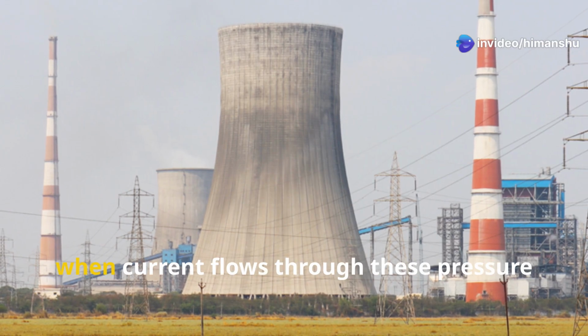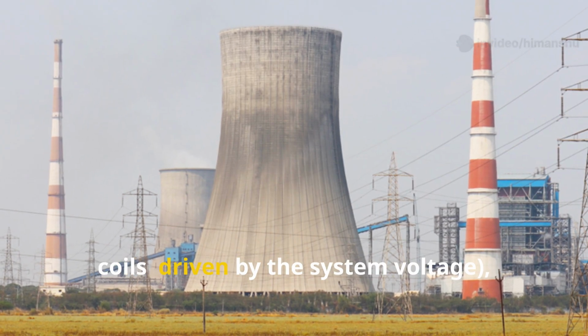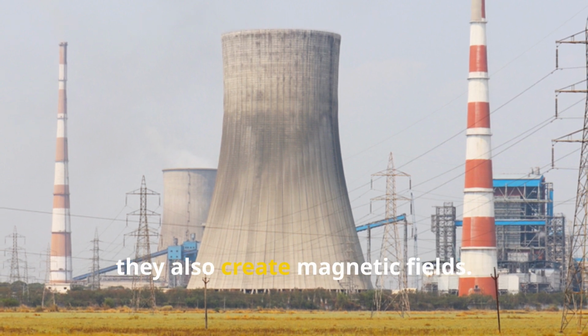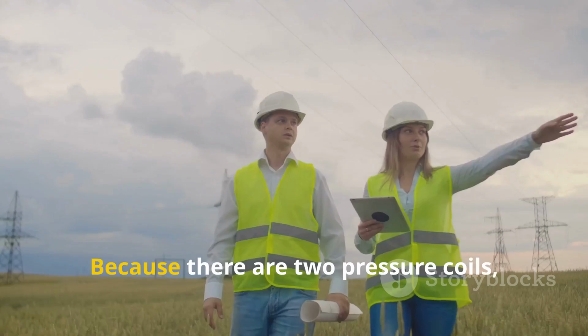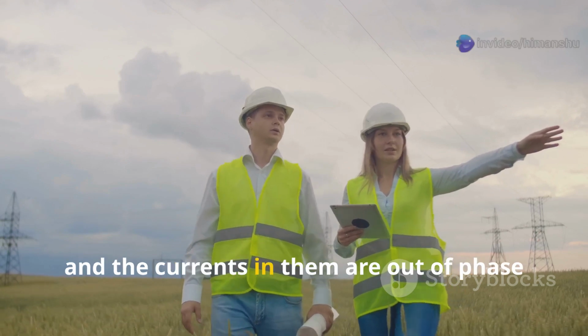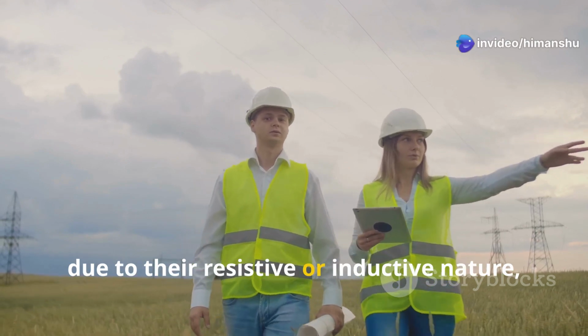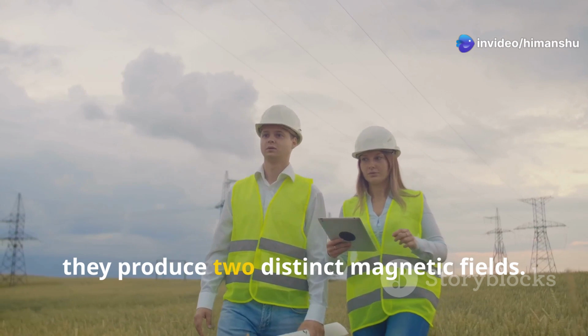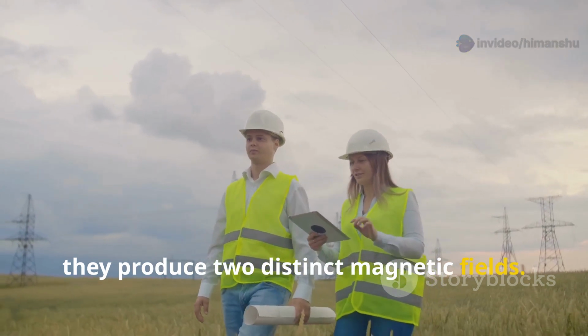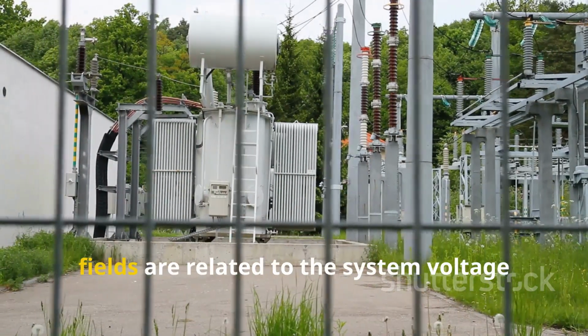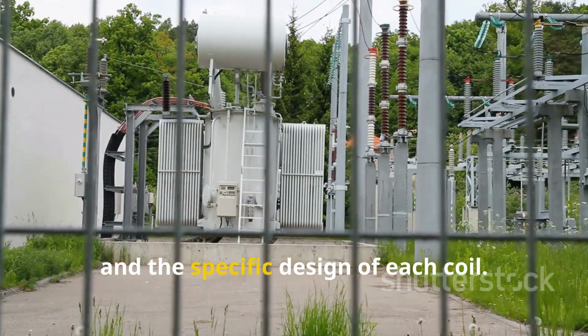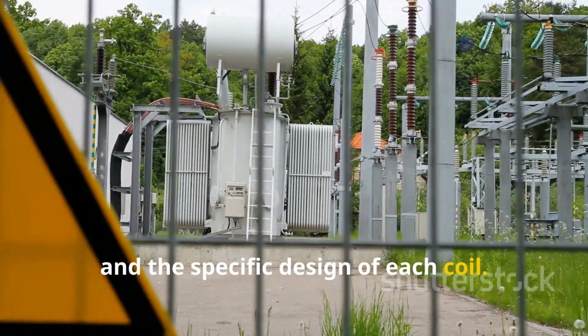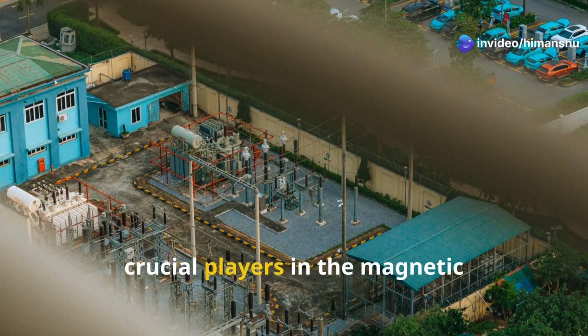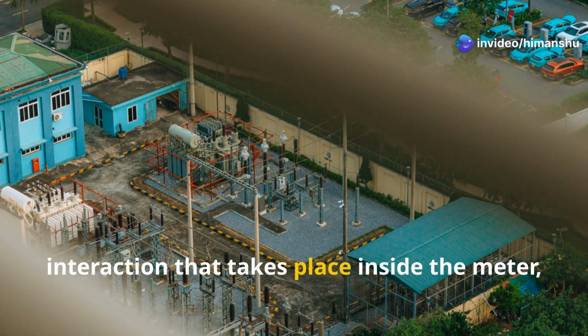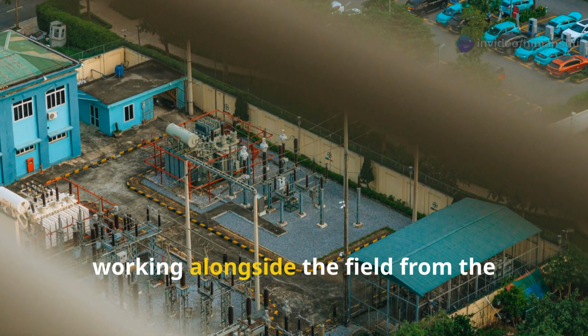Just like the current coil, when current flows through these pressure coils, driven by the system voltage, they also create magnetic fields. Because there are two pressure coils and the currents in them are out of phase due to their resistive or inductive nature, they produce two distinct magnetic fields. The orientation and strength of these fields are related to the system voltage and the specific design of each coil. These magnetic fields are the other crucial players in the magnetic interaction that takes place inside the meter, working alongside the field from the current coil.